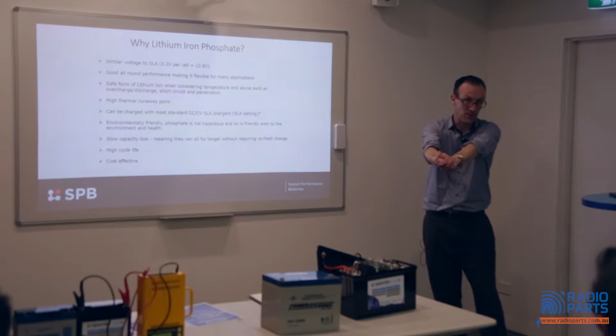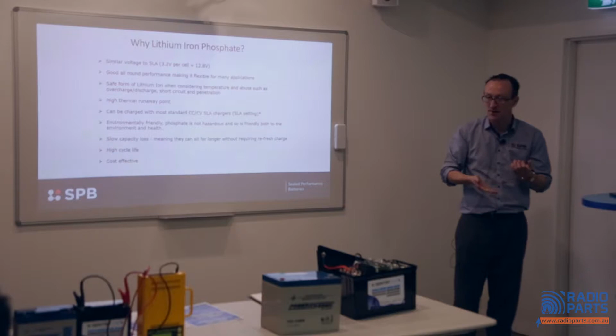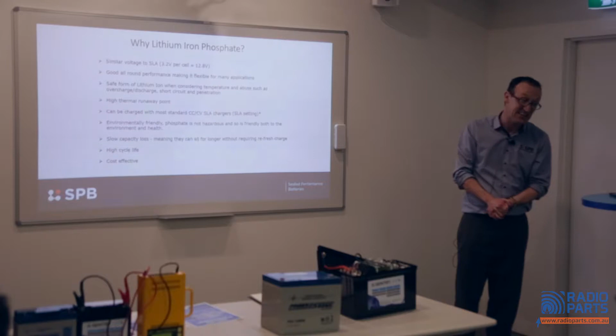Well, here's why: the cycle life. With a lead acid, as you've seen by comparison with that of AGM versus gel, it's not too bad, but I can tell you this: you're going to pay 4 to 5 times the price for a lithium, but your running life in terms of cycle life is going to be 7 to 8 times as long. The initial upfront investment, it treads water when you really look at it. It is viable in the long run, but trying to get people to open their wallets up front, therein lies the challenge. When you consider the long-term advantages, yes, it is more cost effective, but yes, it can be a hard sell. I do not deny that.